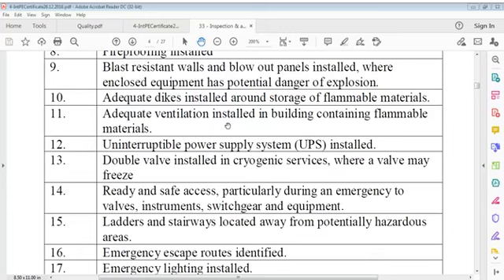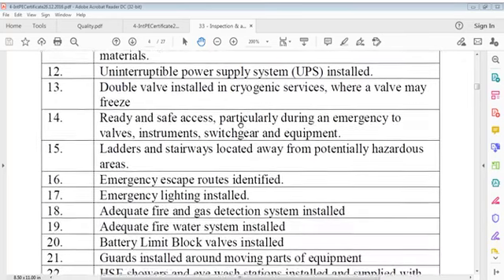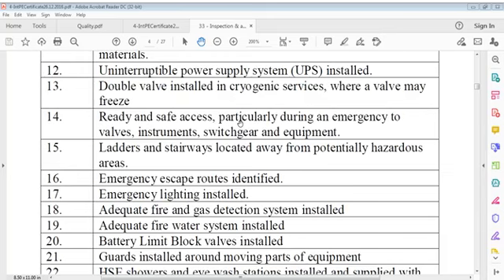Ventilation installed in building containing flammable material. Uninterruptible power supply, which we call UPS, installed from protection viewpoint. Then double valve installed in cryogenic services. Very, very low temperature, minus temperature, is involved. At least we have to keep one valve which should not freeze while the service valve freezes. Then we can take care using that standby valve, even if it is a cryogenic atmosphere, in that pipeline through which this material flows, which should not be chilled, should not be frozen.